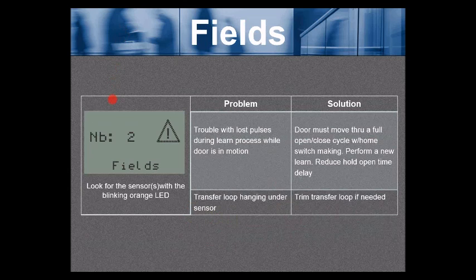Fields error. Again, look for the sensor or sensors with the blinking orange LED. The first number one problem for the fields error is trouble with lost pulses during the learn process while the door is in motion. The solution? The door must, must move through a full open and closed cycle with the home switch making.